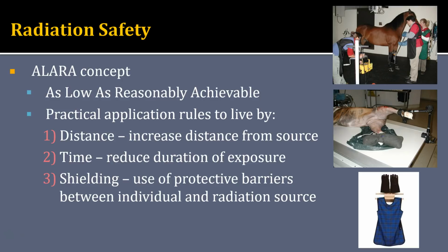And that is 1, thinking about distance. If we can increase our distance from the source, we will really decrease our exposure. The image on the top here shows ways that we can do that. For one, here is our imaging plate, and the staff member here is holding that plate not with their hands but with a plate holder, so that gets them further away. Another method is this X-ray tube. When we expose it, there's a 6-foot cord, so when she's ready to expose the image, she can step away from that X-ray tube by 6 feet. So those are ways to maximize our distance, get as far away as possible.